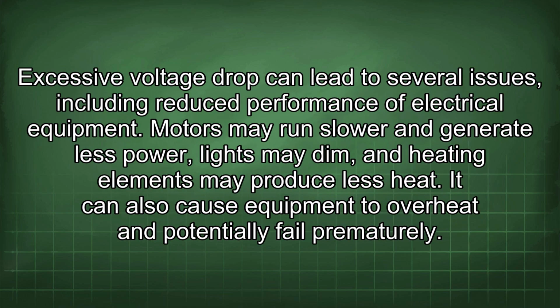Excessive voltage drop can lead to several issues, including reduced performance of electrical equipment. Motors may run slower and generate less power, lights may dim, and heating elements may produce less heat. It can also cause equipment to overheat and potentially fail prematurely.